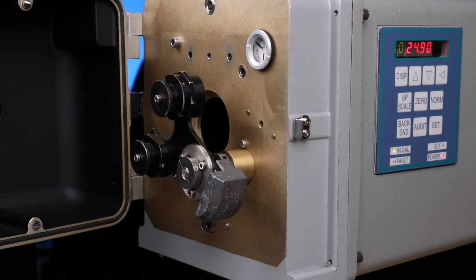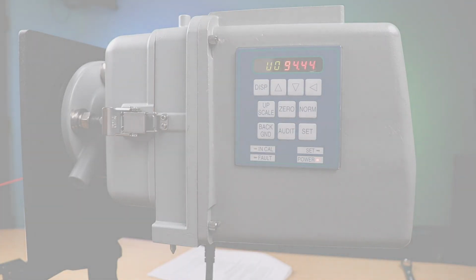After 2 calibration cycles have been performed, the set procedure is complete. Check that the zero in the user bank 6, or U6, is the same as the dust compensation U8. If they are not, perform the on-stack set procedure again. After the 2 cal cycles are complete, note the calibration value in U7 and set the value in C1 and in the DAS to match.